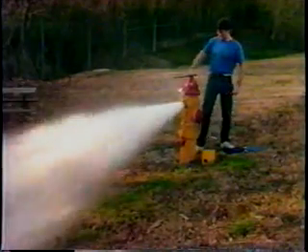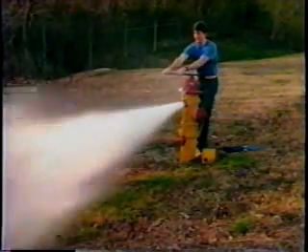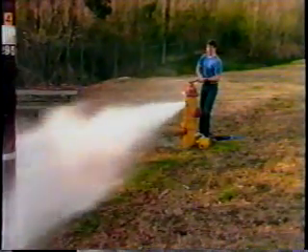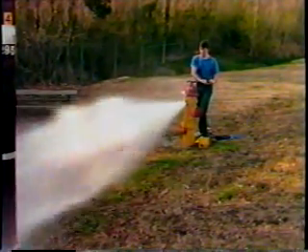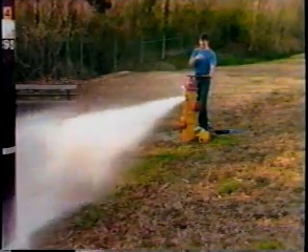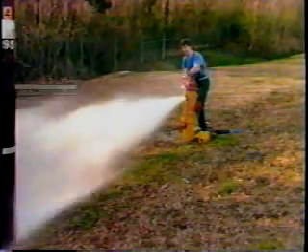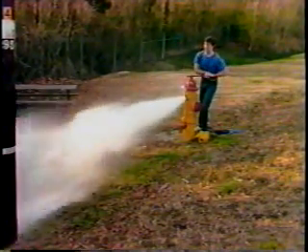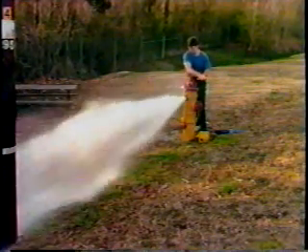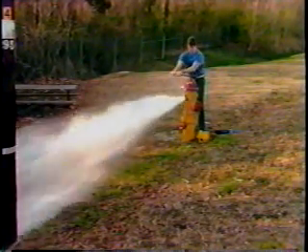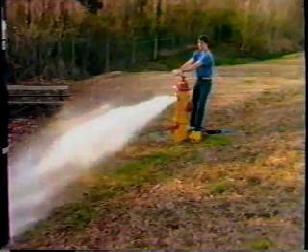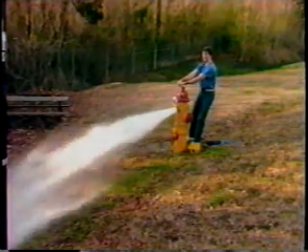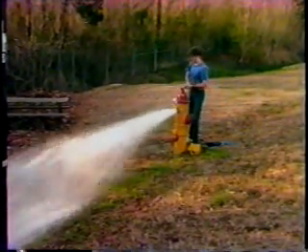When the individual at the residual hydrant is satisfied that the flow test is complete, he will signal to the person at the flow hydrant to shut off the hydrant. Remember, just as you had to open the hydrant very slowly to prevent any surges in the distribution system, you also need to close the hydrant very slowly. The last few turns of the operating nut are especially important. Make sure that you do them slowly, or even stop periodically while you're shutting off the hydrant.